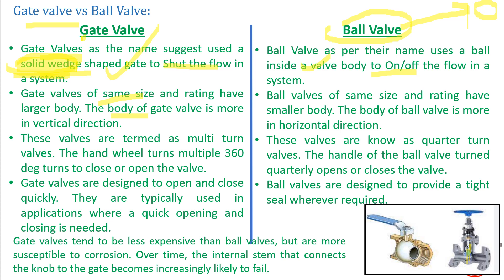For the same size and same rating, a gate valve has a larger body. The gate valve moves in a vertical direction — when the handwheel is rotated, the spindle moves up and down. Compared to a ball valve of the same size and rating, the gate valve will be larger, while the ball valve will be more compact. If the size of the ball valve increases, it increases in the horizontal direction, while the gate valve extends in the vertical direction. Gate valves are also termed multi-turn valves because the handwheel needs to be rotated multiple times to move the wedge-shaped spindle.